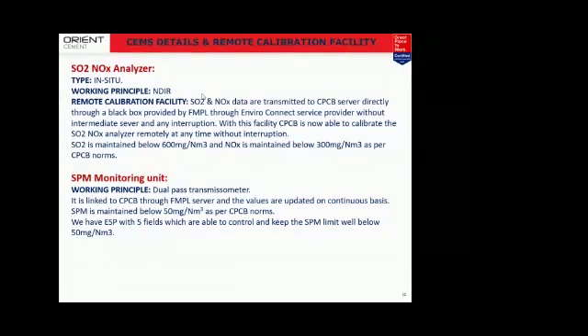The remote calibration facility was incorporated in the year 2018. Both SO2 and NOx data are transmitted uninterruptedly to CPCB directly through a black box. The black box is nothing but a transmitter which transmits the data directly from the SOx NOx unit to the CPCB without any intermediate servers. That is also provided by Forbes Marshall, and we are also transmitting the data through the Forbes Marshall server only, that is, EnviroConnect is our service provider. With this, we are facilitated to have remote calibration. That means CPCB can at any time do a remote calibration without any interruption.